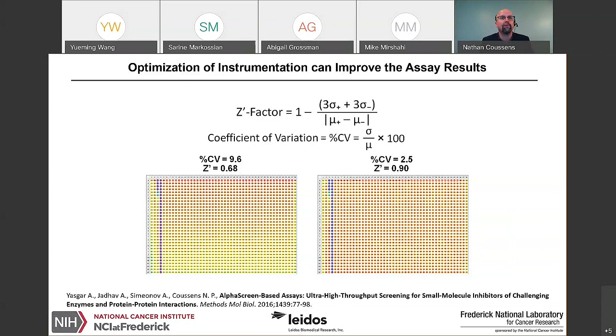This is, again, a 1536 well plate shown as a heat map. Red is high signal, purple is low signal. You see this gradient here. And when I flipped the plate, the gradient stayed in the same position, indicating it was with the plate reader, not the plate. When we optimized the settings of this instrument, you can see the percent coefficient of variation improved by 75%, improving our Z prime factor from 0.7 to 0.9. And so that resulted in a lot of improvement in the assay performance.